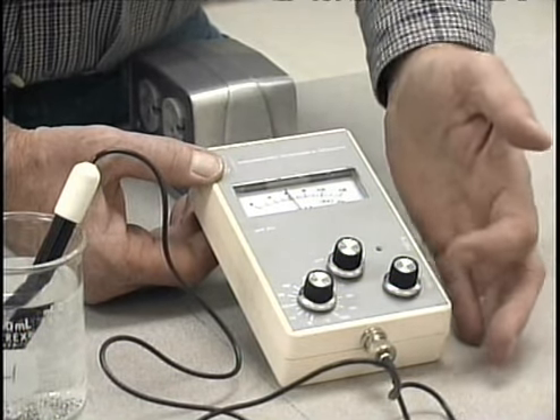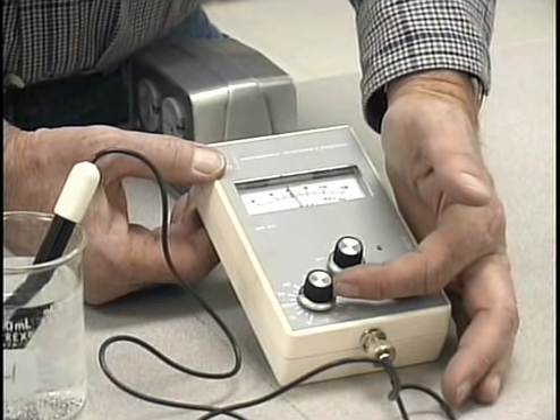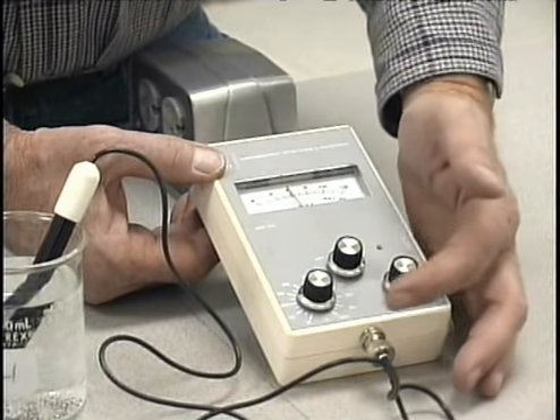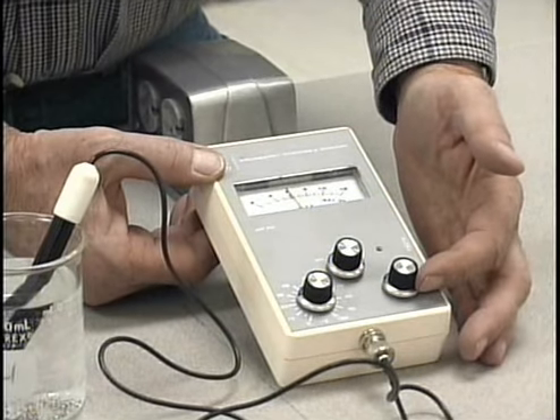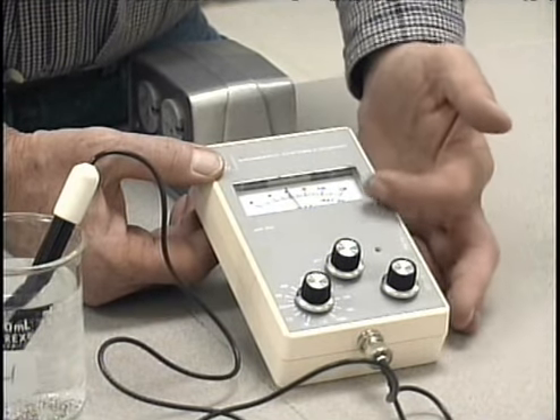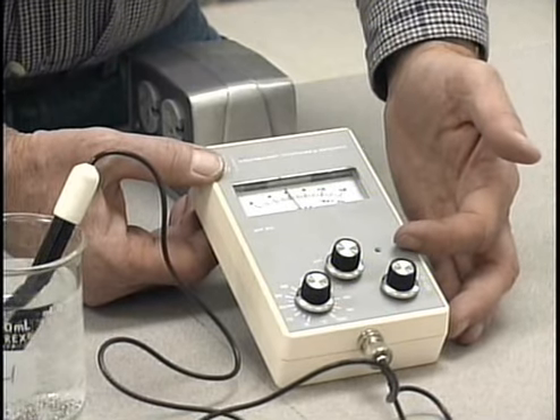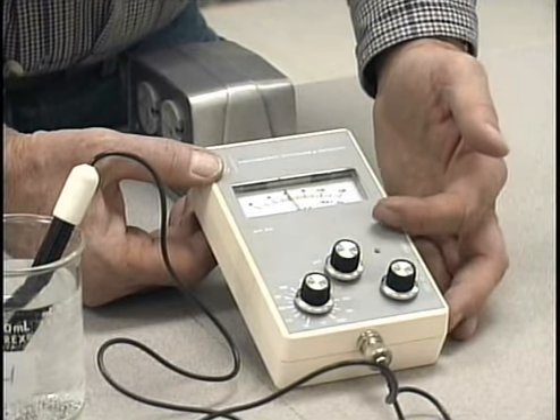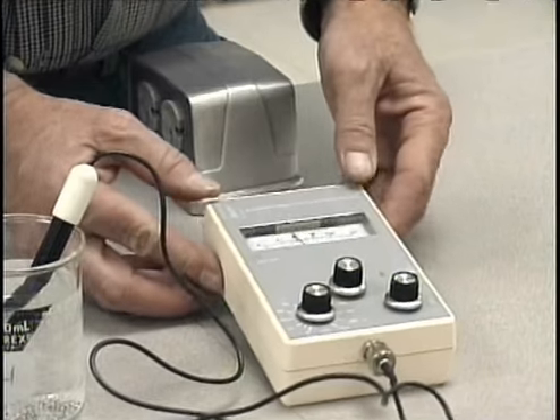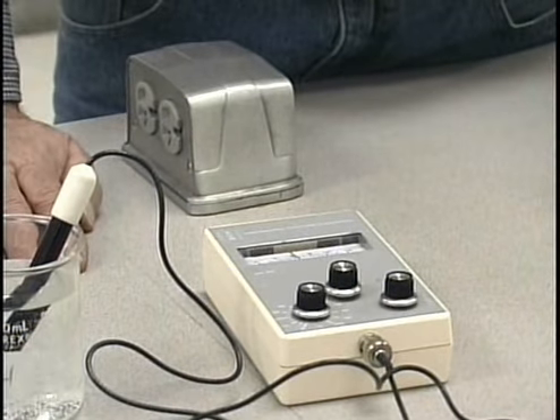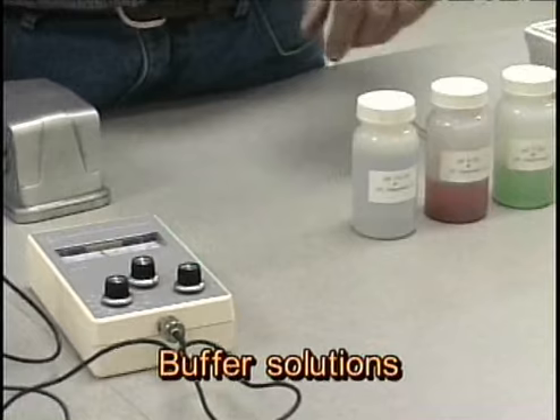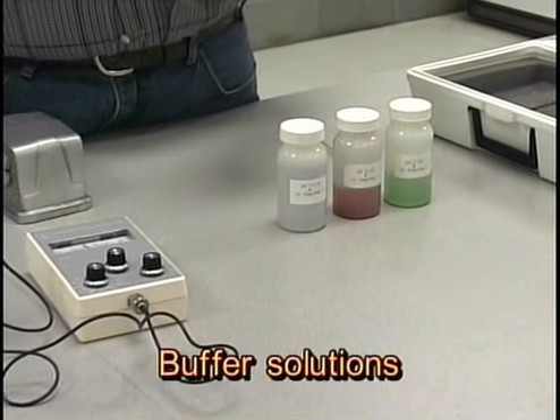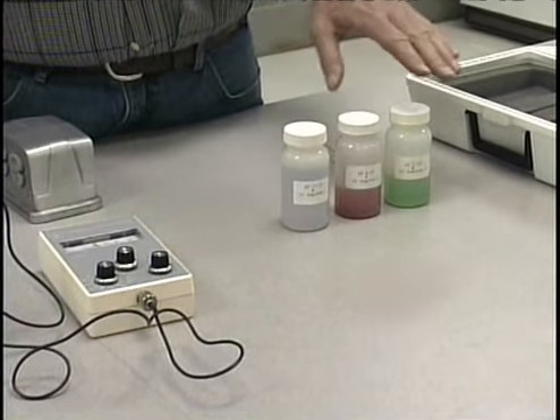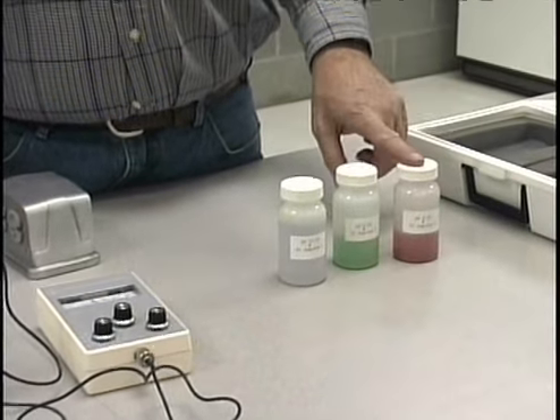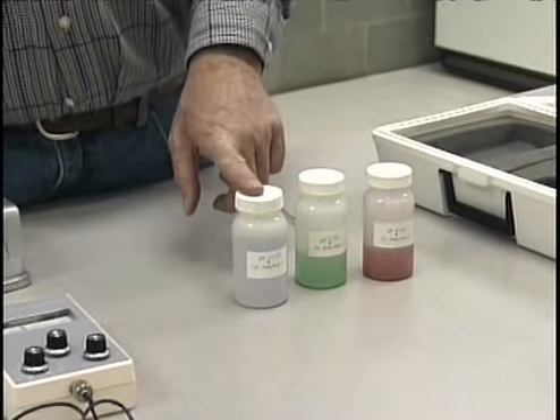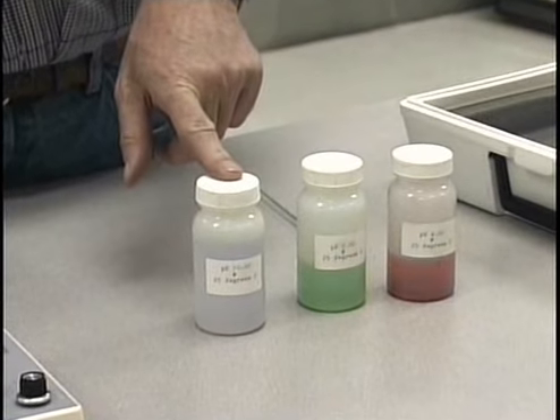Calibration of pH meters is accomplished for both temperature and pH. We set the temperature based upon the temperature of the solution which it's in, and we also have a standardization knob here which allows us to adjust for the pH reading. When I say adjust for the pH reading, prior to the time we start taking the readings, we are going to be utilizing a series of buffer solutions which are at a set or constant pH. Because we have a range of pHs here, we have solutions that run from 4 on this end to 7 to 10. And that's fairly standard for pH buffer solutions.